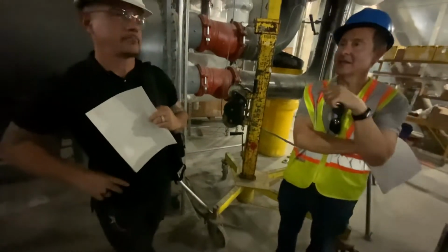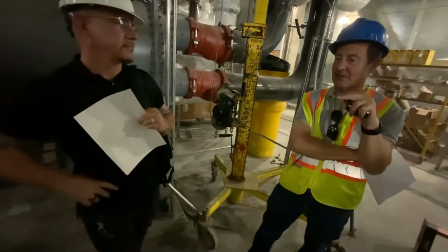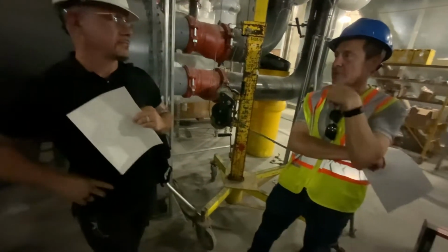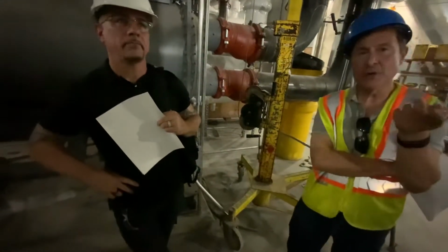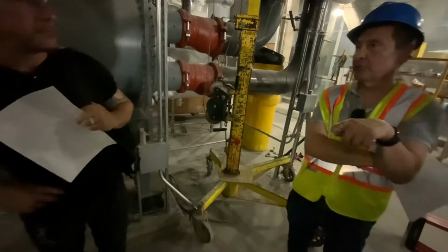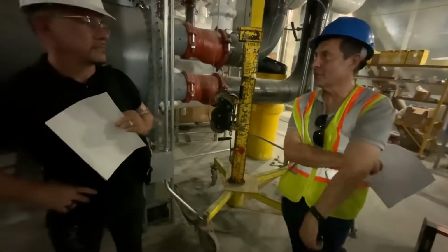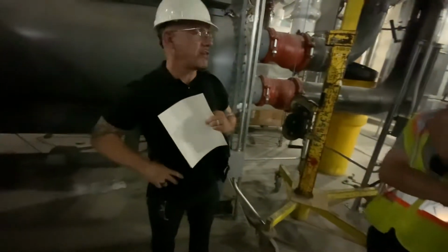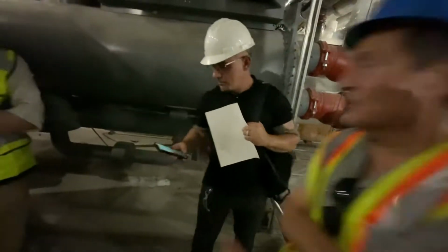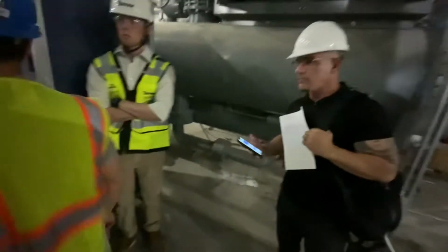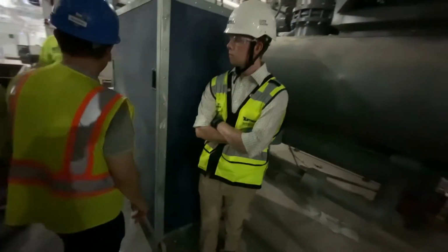Yes. But that's not the actual load of the device that's supposed to protect them. It's just the maximum you can go to. Right. UL requires that. It's a code thing. You have to label it. So if you do the math on the actual full load amps, an 800 amp breaker works just fine. And you're never going to start them all up at the same time. Correct. Plus they ramp up slowly, they soft load.